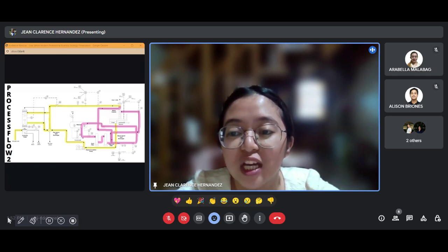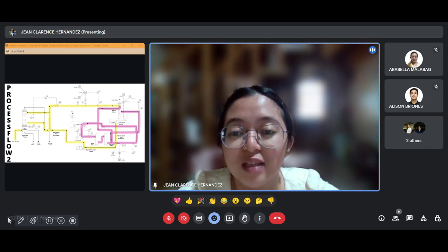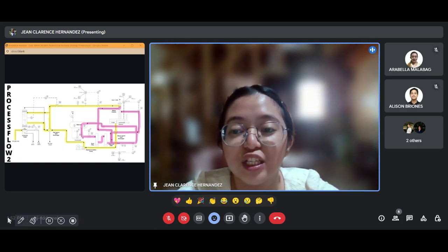Following a heat exchange with the lean glycol, the rich glycol undergoes separation of its components in the skimmer. Subsequently, it passes through a sock filter and charcoal filter to eliminate additional impurities and hydrocarbons. After this, it flows through the first glycol heat exchanger before returning to the reflux column.